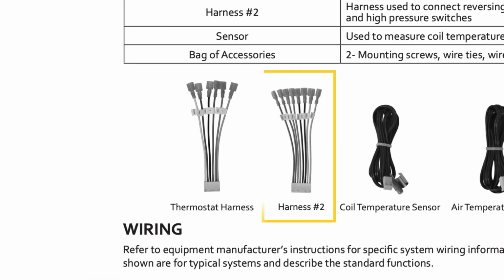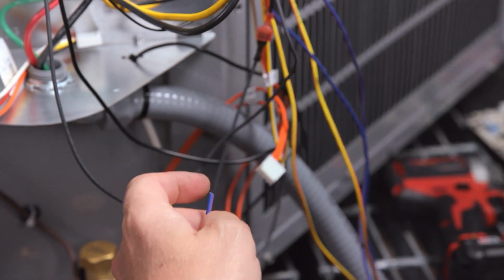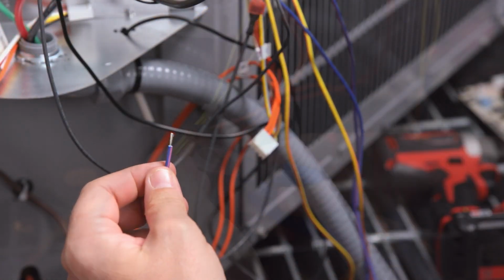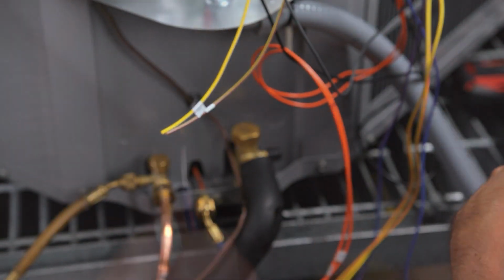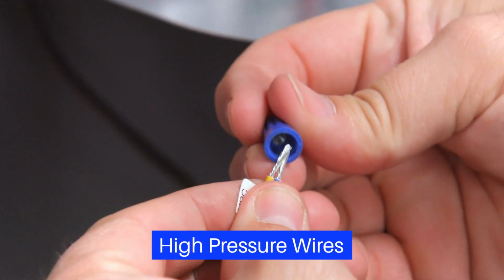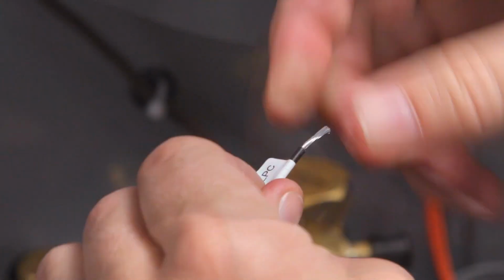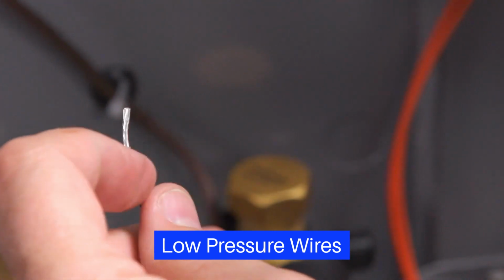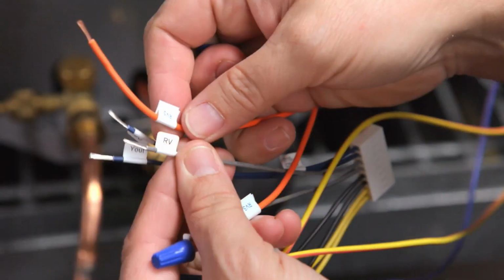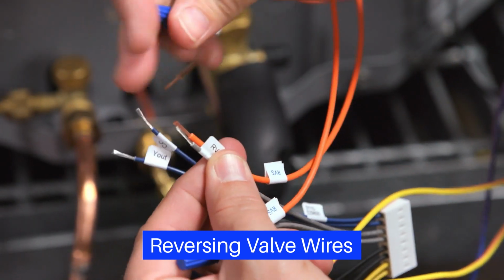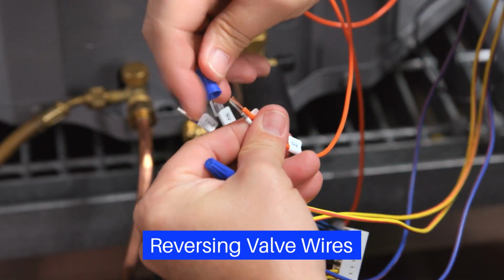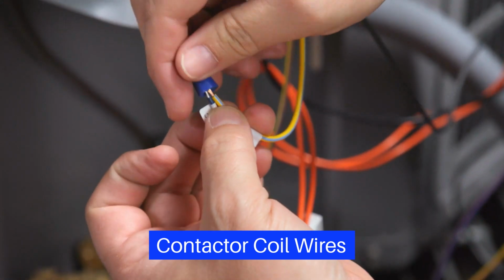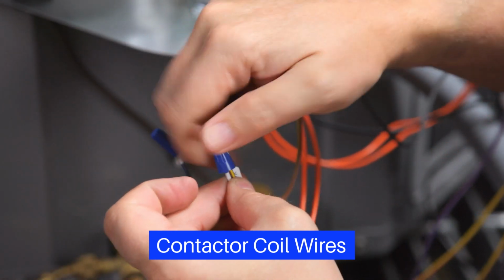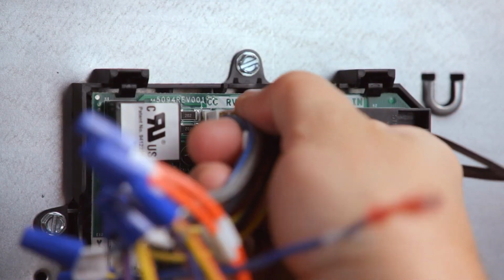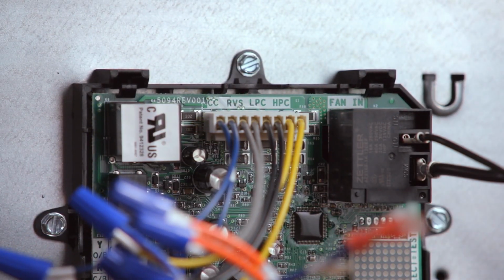Identify the harness number 2 to begin wiring. The wires can be connected by installing spade connectors or by cutting off all connectors and using wire nuts. Attach the high pressure wires to the wires labeled HPC on harness number 2. Next, attach the low pressure wires to the wires labeled LPC on harness number 2. Then attach the reversing valve wires to the wires labeled RV and RVC on harness number 2. Finally, attach the contactor coil wires to the wires labeled CC and Y out on harness number 2. Now plug harness number 2 into the 8-pin inline connector on the board.